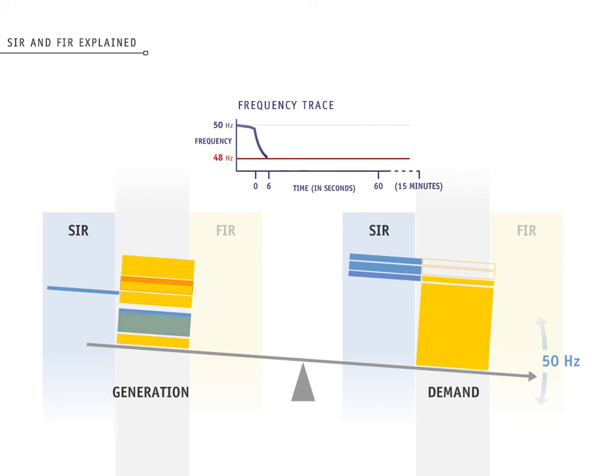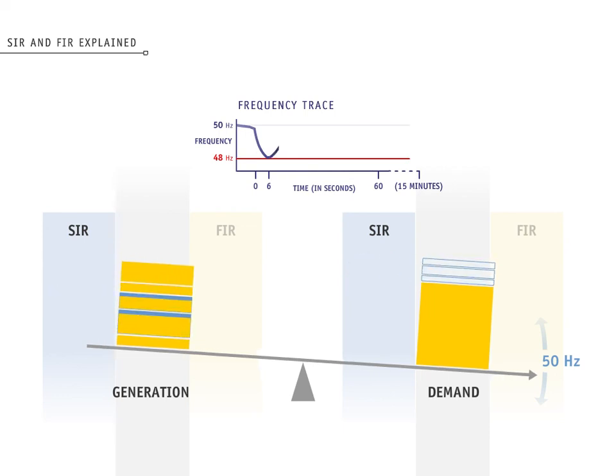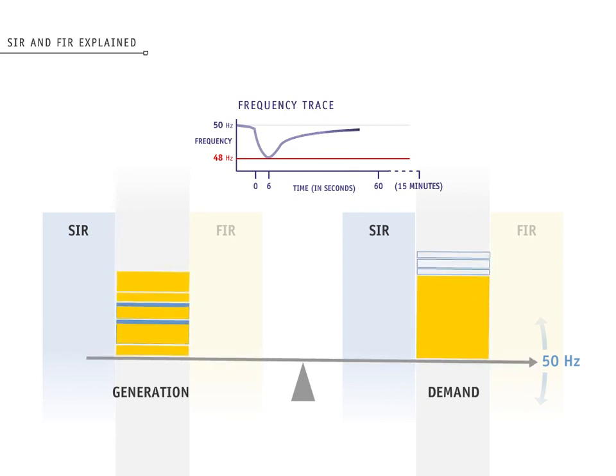The oncoming sustained instantaneous reserve, or SIR, within the first 60 seconds, will restore the frequency to above 49.25 Hz and last for 15 minutes.